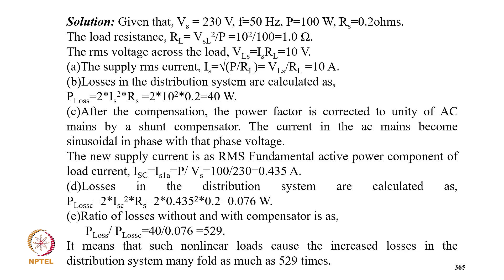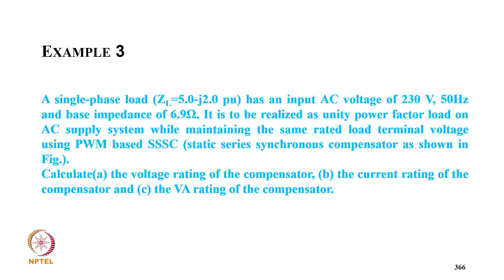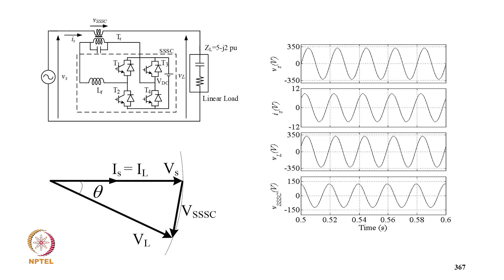Coming to example 3. A single phase load has an input voltage of 230 volt, 50 Hz, and a base impedance of 6.9 ohm. It is to be realized as a unity power factor load on the AC supply system while maintaining the same rated load terminal voltage, using a series static synchronous compensator shown in the figure. Calculate the voltage rating of the compensator, current rating of the compensator, and the VA rating of the compensator. This is a typical case of how we are injecting the voltage in series, and you can see the phasor diagram as well as the waveform.